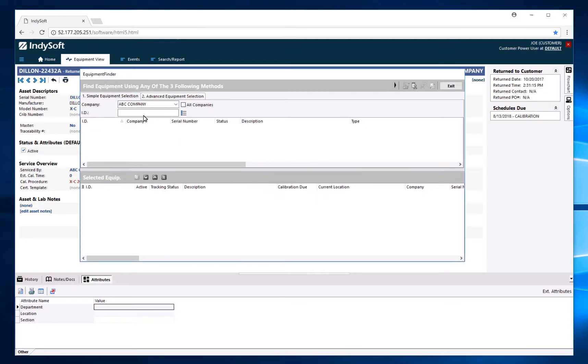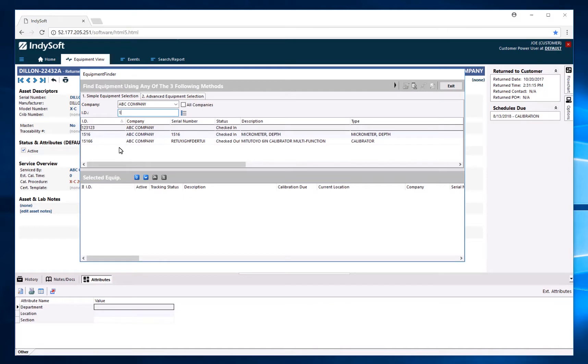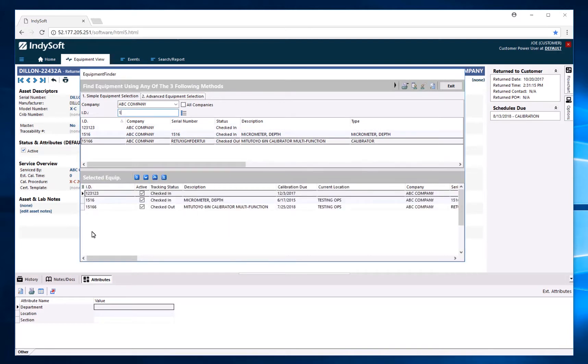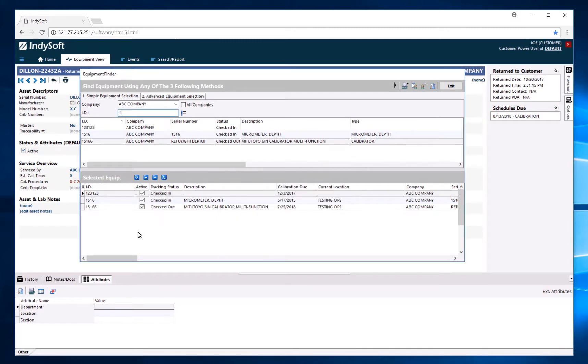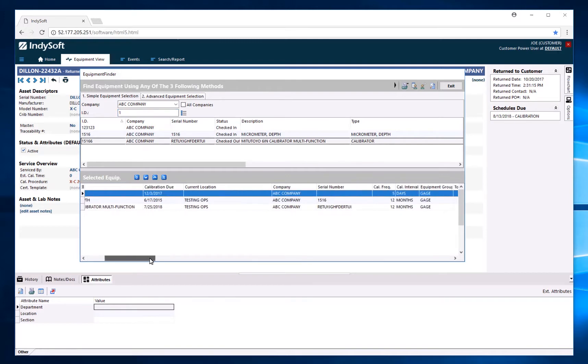Let's go back to ID and look at a few assets. If you want to mass print all the certificates for these assets, simply hit the double blue down arrow to bring them all down, then go to the printer and select 'print certs for all equipment'. This will print all certificates for this equipment, and you can filter by a specific date range for all calibration events that occurred within that range — then just hit OK.